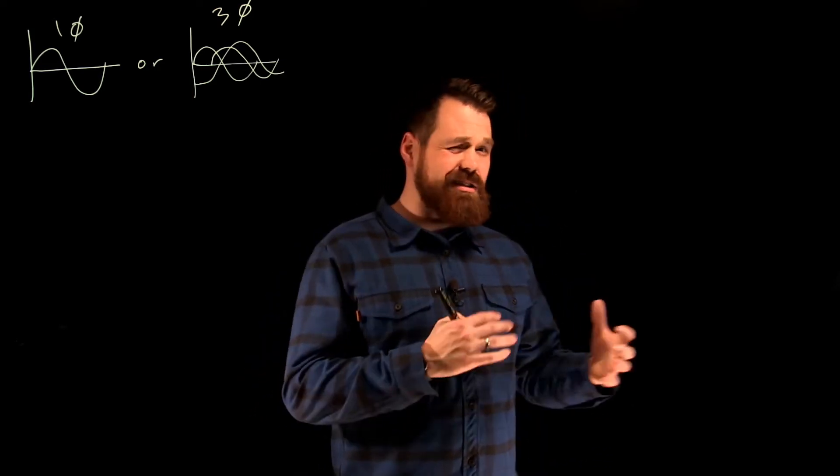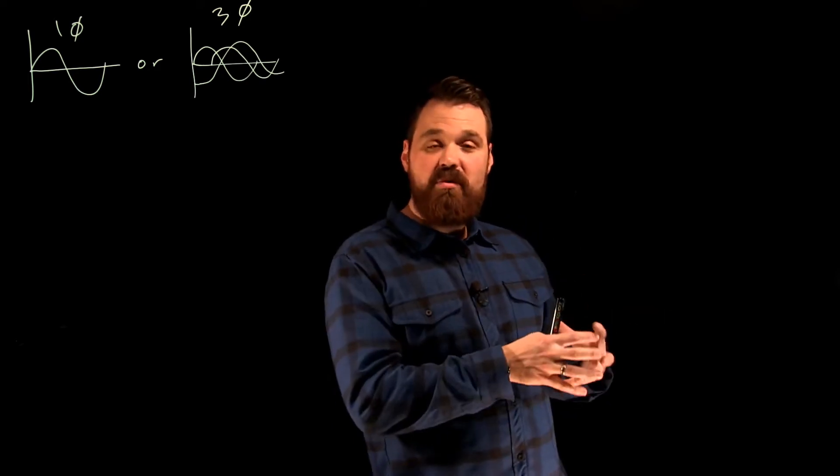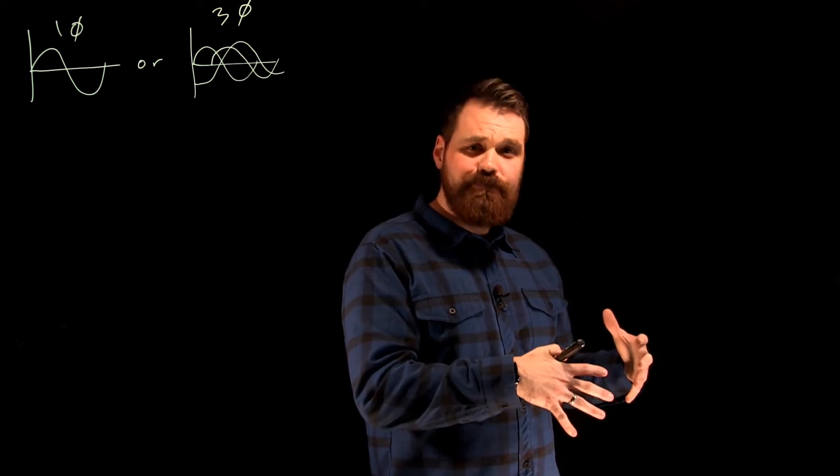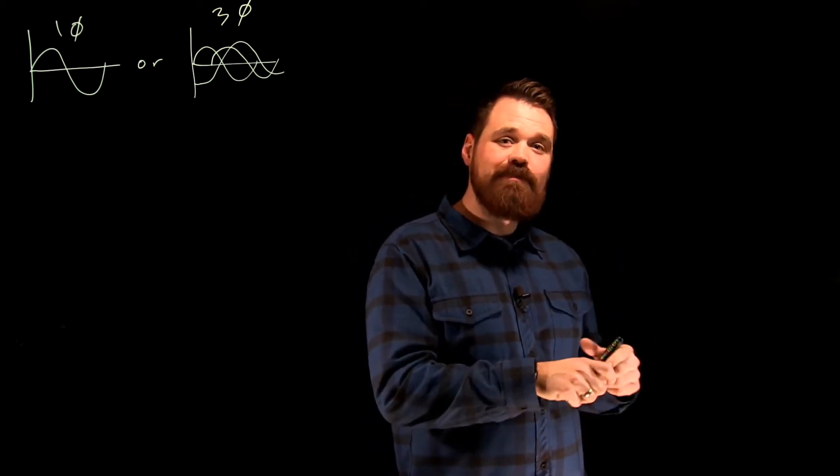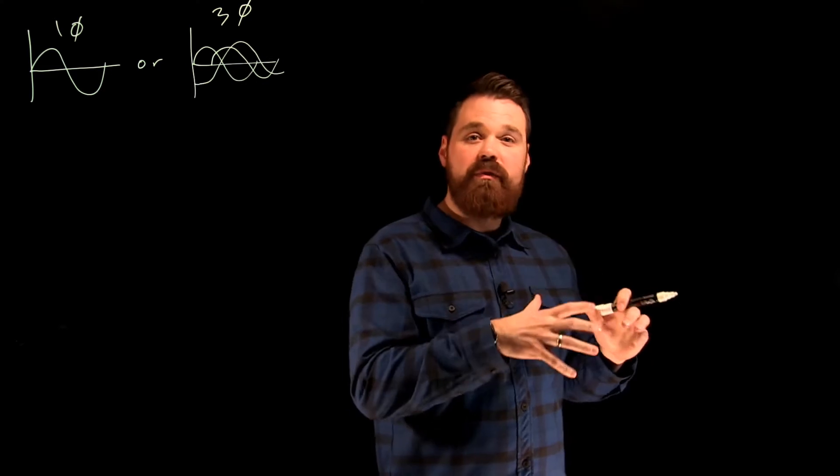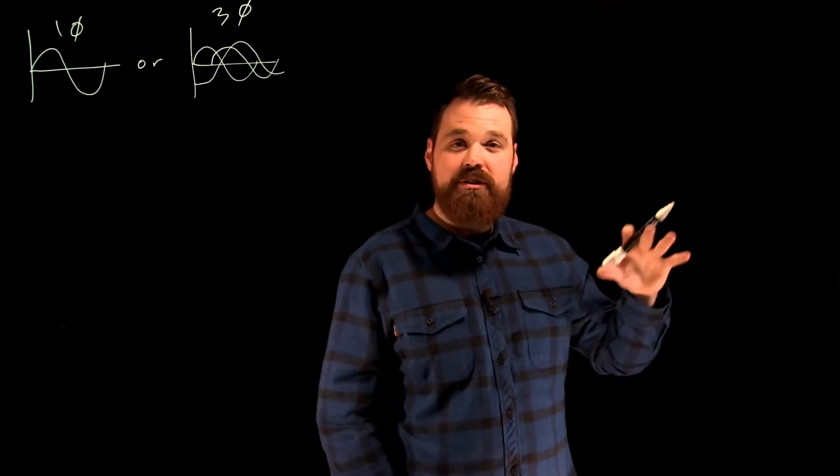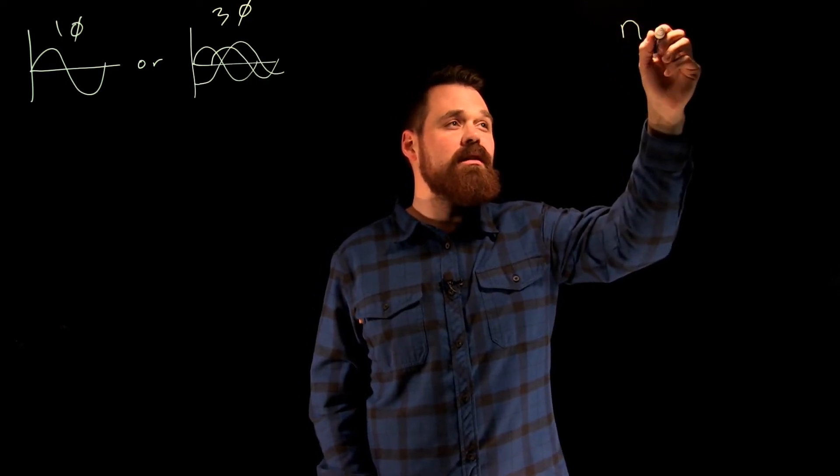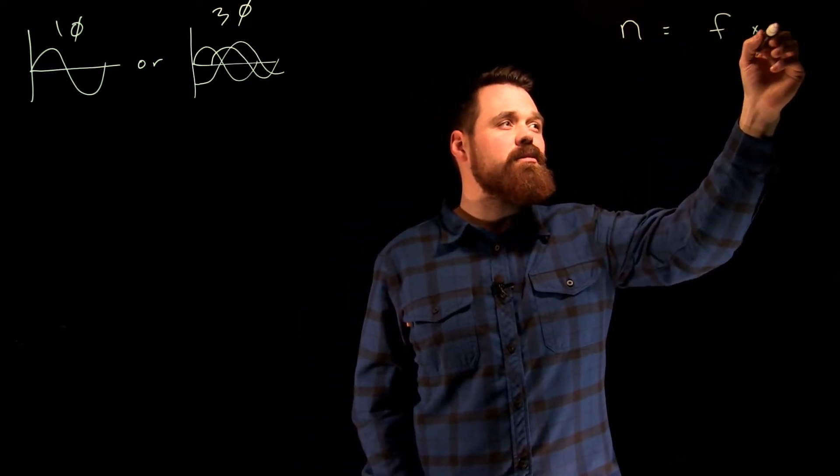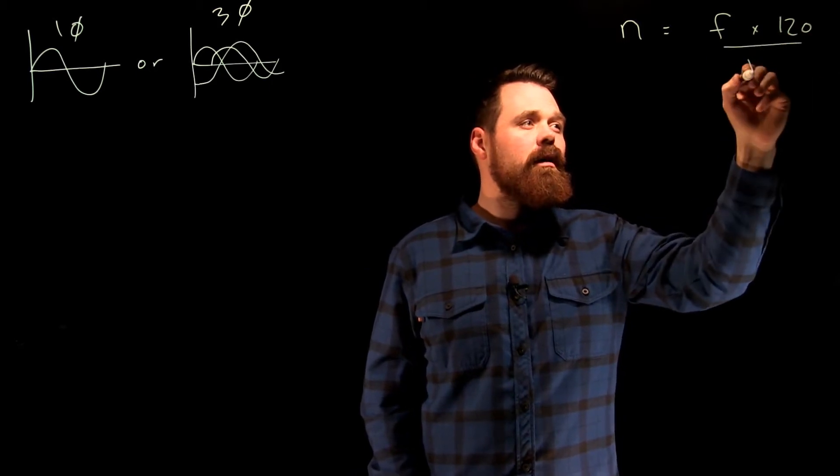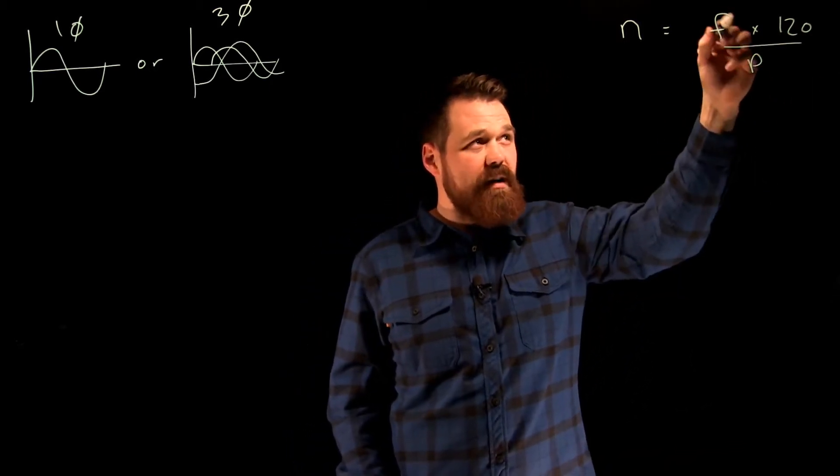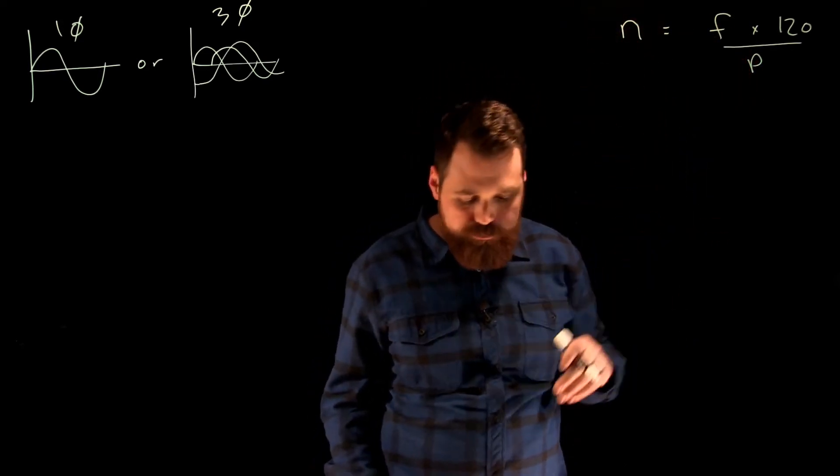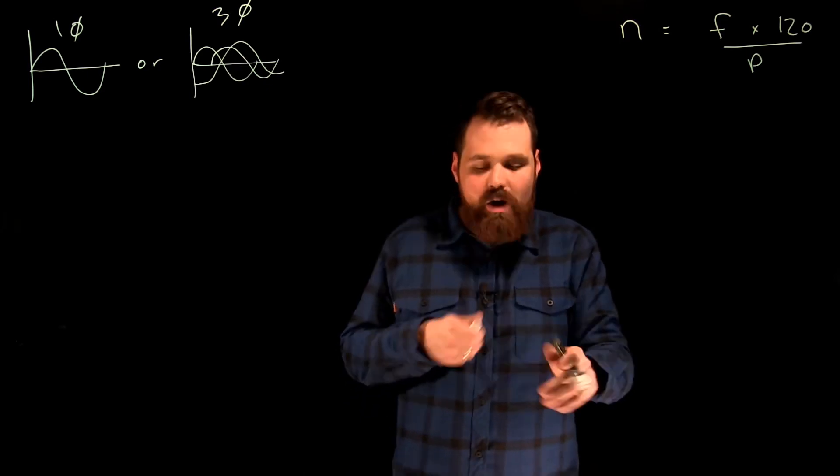It's not practical to change the number of poles inside a motor to get variable speed. So we use our frequency formula: frequency equals poles times speed over 120. By varying this frequency, we can easily change that synchronous speed of the motor.